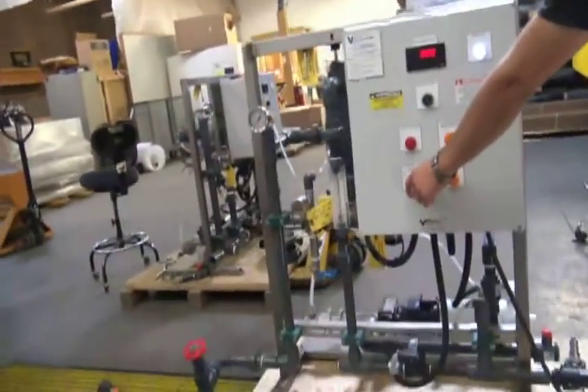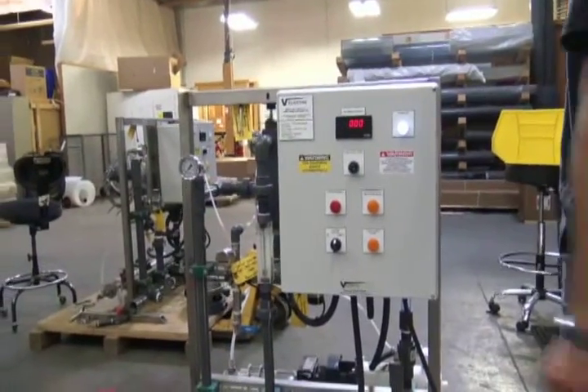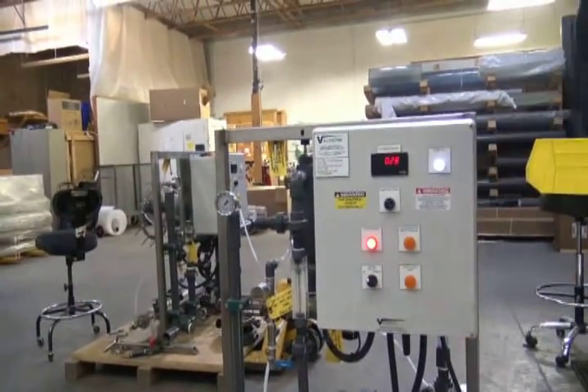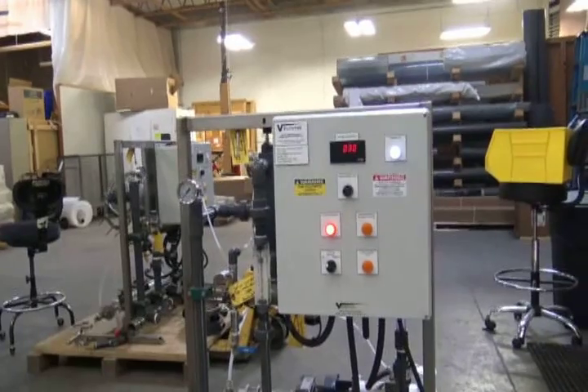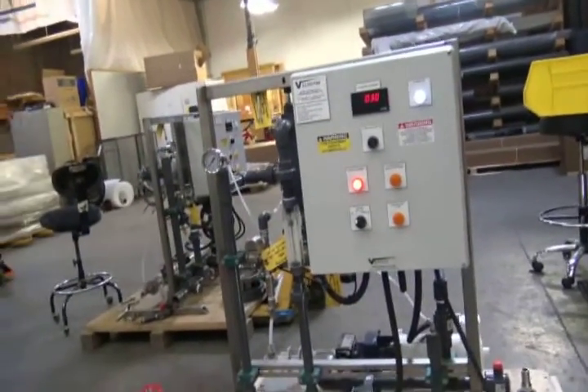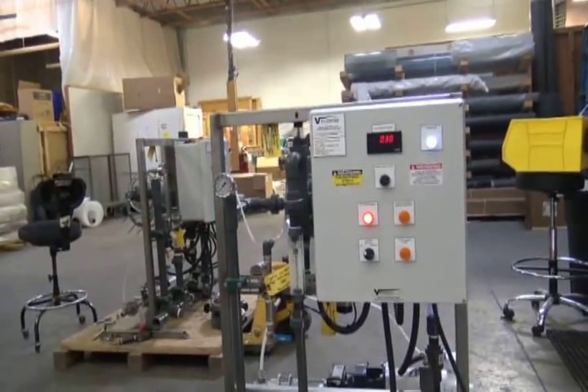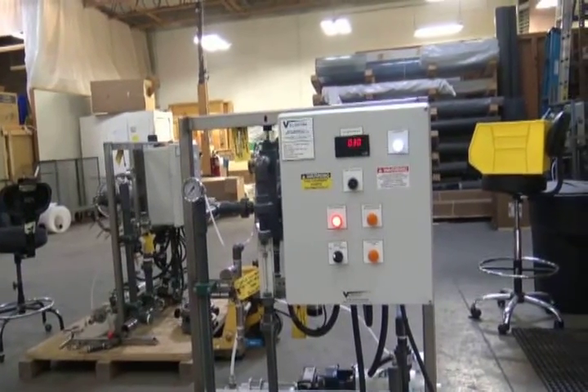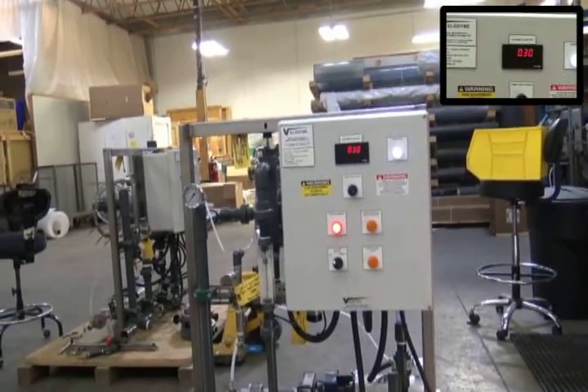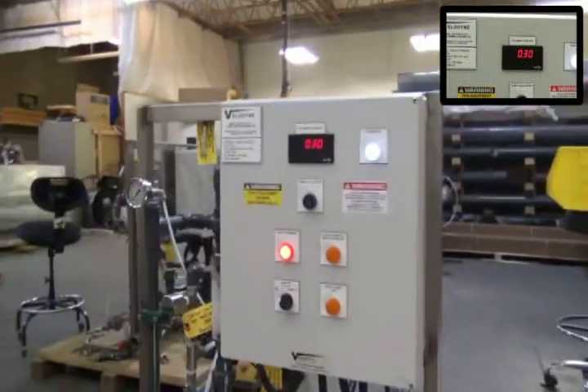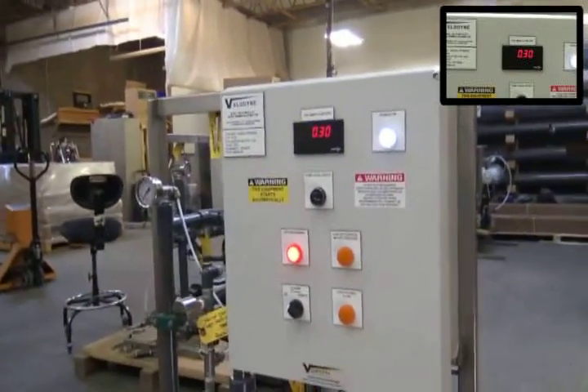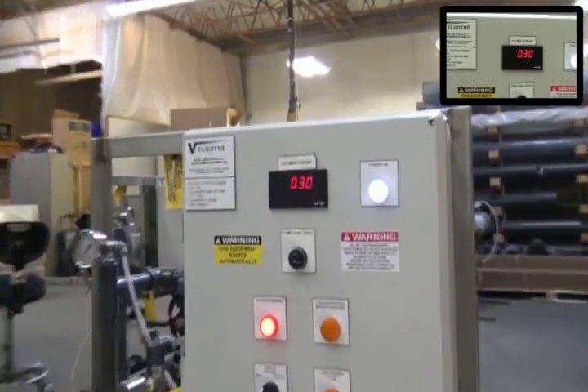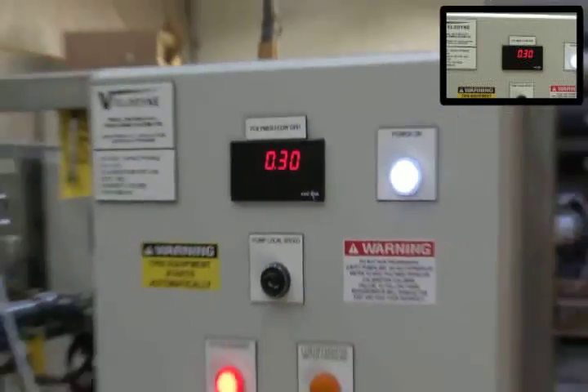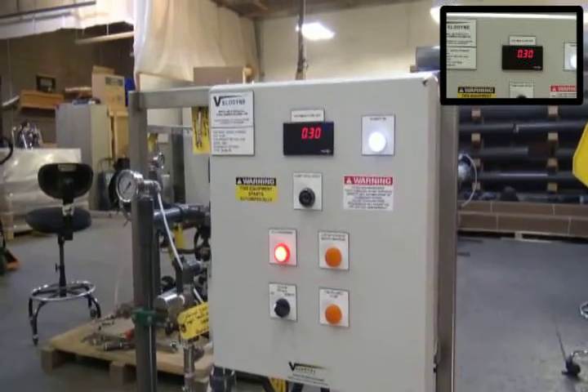I'm going to have my coworker help me out here, and we are going to show you how to do that. First, we turn the system on and let it run for a little bit to make sure that it settles out and we are getting the best flow that we can going through the thermal flow sensor. With that being said, we've already set this one at the 0.3 gallons per hour on the display here.